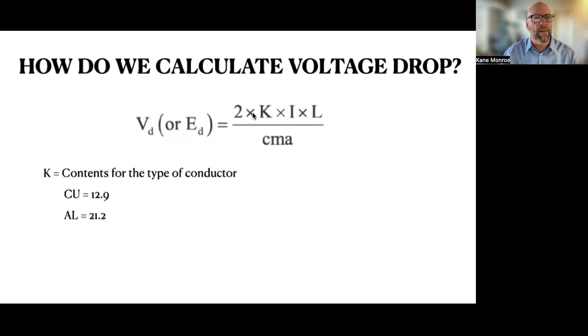Alright, so what does K stand for? K is the constant, and that depends on the type of wire that you're trying to figure out. For copper, we use 12.9 as a number, and aluminum is 21.2. Those two are always the same depending on what material you use.